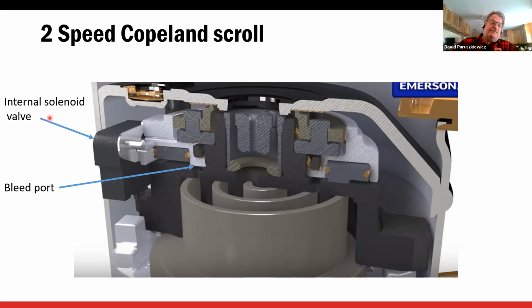Easiest way to test that is put it on high stage, second stage, and then unplug that valve, and you should hear the compressor. You should hear it actually engaging and disengaging. So again, all that does is open the bleed port. There's one here, and it allows gas from this side to dump back into the suction side. So we're unloading it, if you will. Again, the solenoid energizes to close it. Easiest thing to do is unplug, put it in second stage cooling, unplug the solenoid, and see if you definitely hear a change in sound of the compressor. You can put your amp meter on it. You'll see the amperage change.